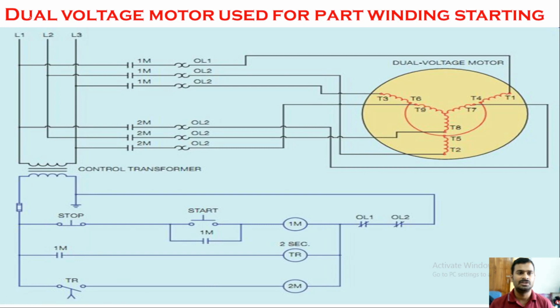Actually, here this dual voltage motor is used for part winding starting. It is only used for part winding starting. This is just to understand how the part winding method is connected here, but in actual practice we need not have this timer and everything. In case you want a star connection, here it is permanently connected in a low voltage configuration. Though it is a dual voltage motor, it is connected in a low voltage star configuration, and it is started that way when we are starting this.